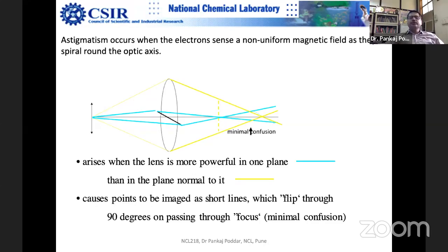And during operation also, lenses undergo a lot of damage. Please remember that pole pieces undergo constant bombardment of electrons. The same problem we discussed about apertures, that apertures can get contaminated and that contamination can lead to astigmatism, can happen to the pole pieces. So please remember, all the debris from your sample, all the things flying from your sample, volatile chemicals, solvents, and all kinds of things finally land up.